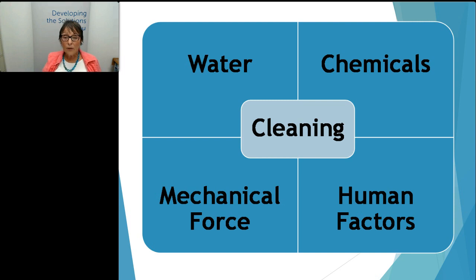Chemicals are certainly an important part of cleaning. But ironically, although I represent a company that manufactures chemicals, I'm going to tell you that chemicals are not magic. You can't just say, oh, as long as I have the right chemical, it'll all be clean. That's not true, because the other two factors are so important. No matter how great your chemicals are, you do have to do things the right way as the human factor, so that you've set things up correctly. And there is always going to be an issue of mechanical force. No matter what it is you're cleaning, in some fashion or another, there's usually some issue of mechanical force that helps to ensure cleaning. So all four of these factors really play into everything that you're doing with cleaning.